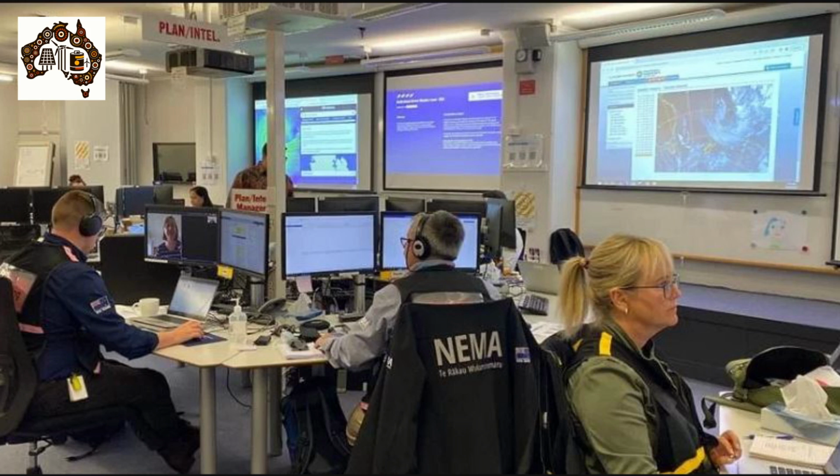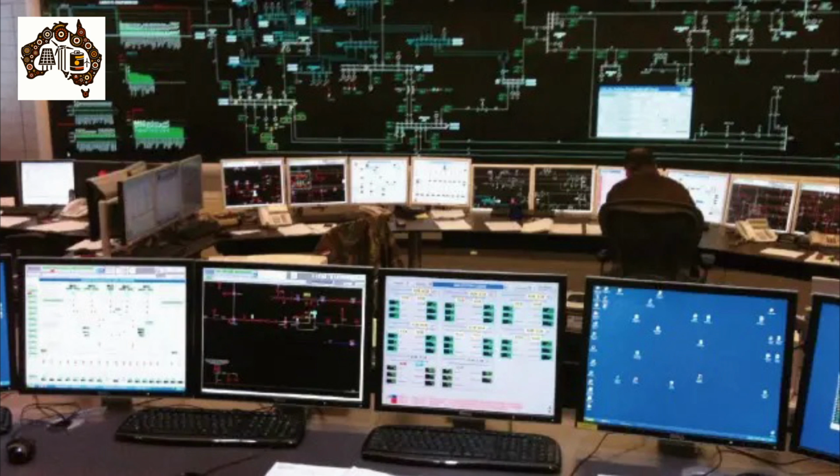This control is made possible through supervisory control and data acquisition (SCADA) systems, where network devices continuously report their current status, operational parameters, and overall health. Therefore, from this last SCADA high-voltage network control point to the downstream customer's electricity meter, distribution network service providers rely on Internet of Things infrastructure, primarily if customers have advanced metering infrastructure, such as smart meters. It's worth noting that for customers with traditional manual electricity meters, DNSPs depend on customers reporting outages through phone calls.